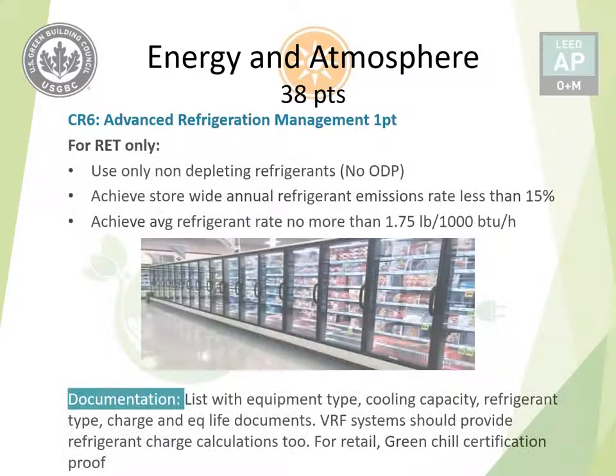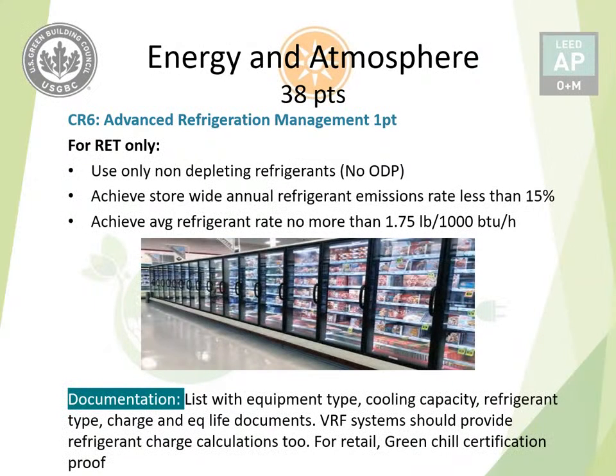And for retail, just like BD+C, there are some extra requirements. The first is to have non-depleting refrigerants, no ODP. Store-wide annual emissions rate should be less than 15%, meaning the leakage rate should be less than that. Average refrigerant charge rate should be no more than 1.75 pounds per 1,000 BTU per hour.